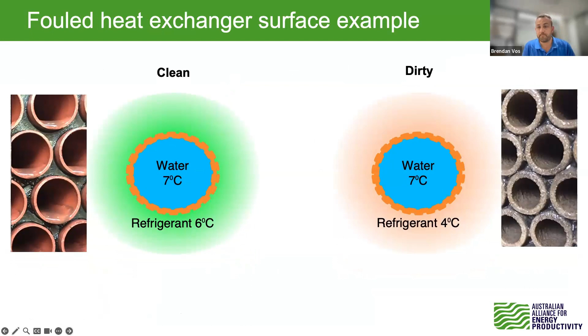So let's assume here we have a chiller running and I want 7-degree cold water, and I have nice clean tubes, which don't look anything like those big pipelines we just saw. These are nice and clean. The refrigerant is 6 degrees. And when they're dirty, we'll have water at 7, but our refrigerant will be at 4. What does that mean? Well, the efficiency measure we call in this industry is thermal approach. That's just a measure of the difference between these two temperatures. So in this case, 1 versus 3, the right-hand side, 3, being much less efficient.